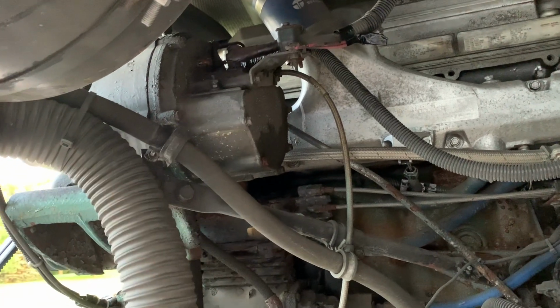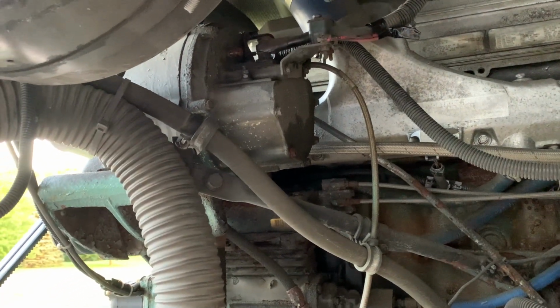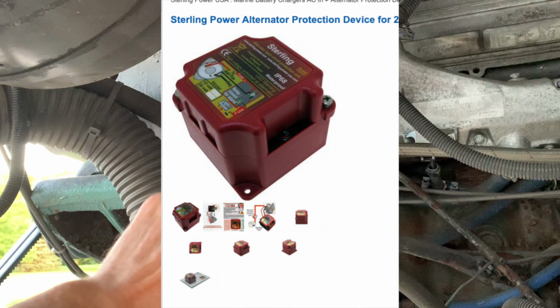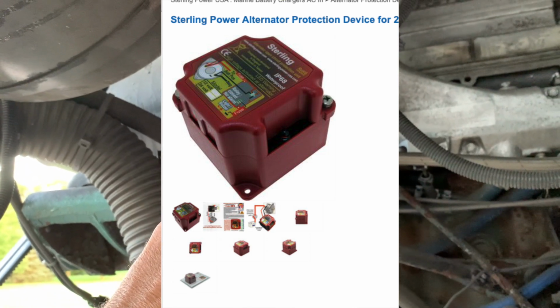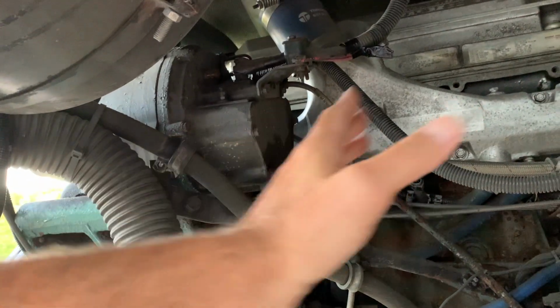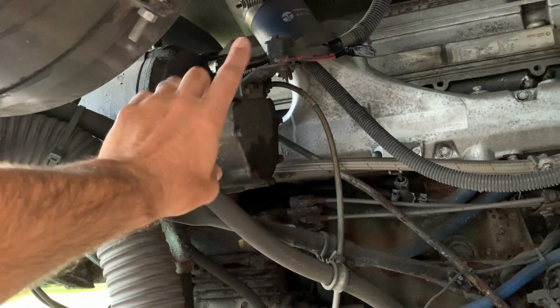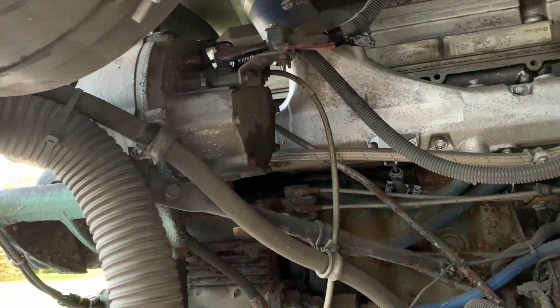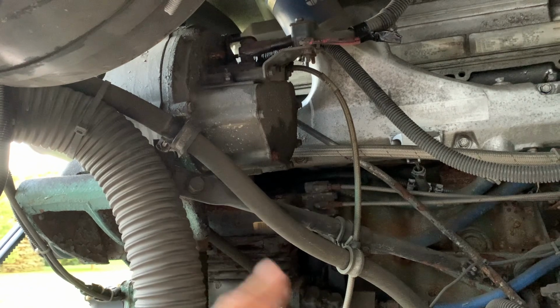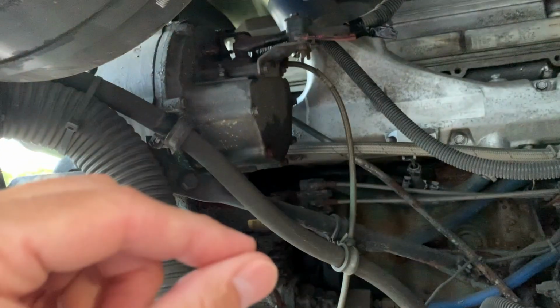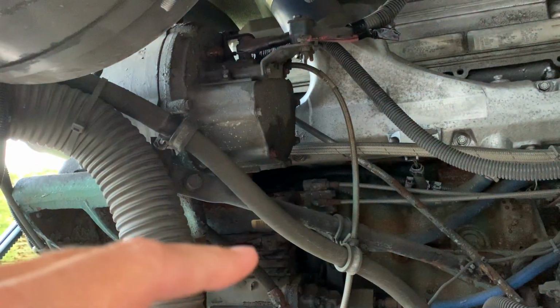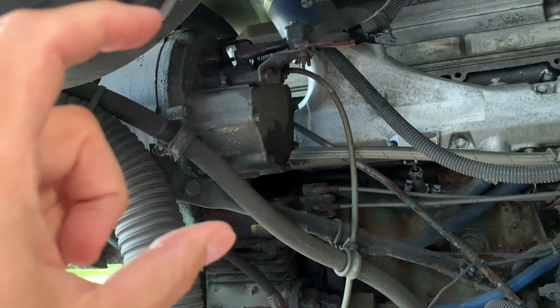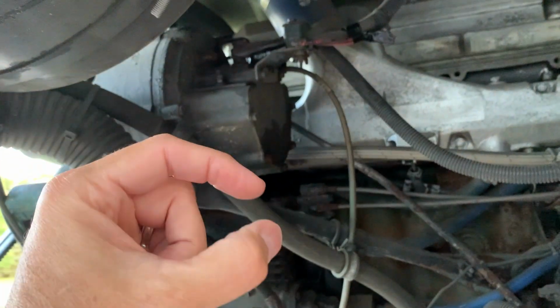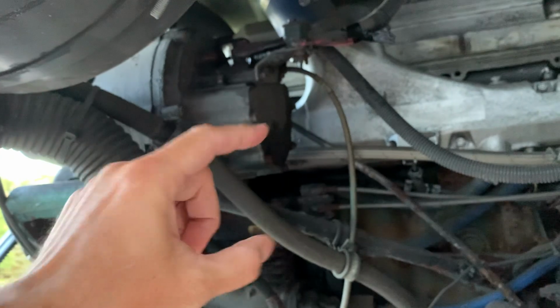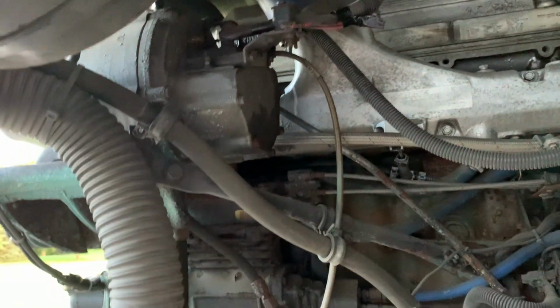So I found this other device, called a Sterling alternator protection device — I'll put a link and picture up here. What that does is, in the event that happens, it will dissipate that voltage spike out. The voltage spike can go up to infinity, but as the voltage goes up, the current goes down, so it's very low current, very high voltage, and it doesn't take much wire. It's supposed to dissipate that out.